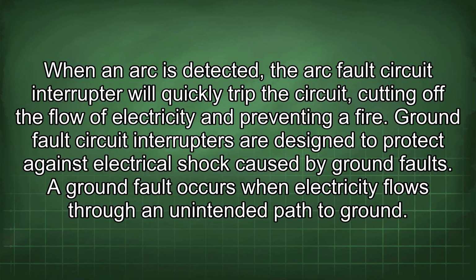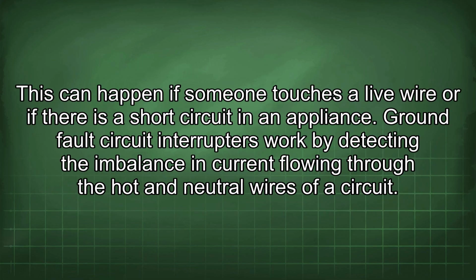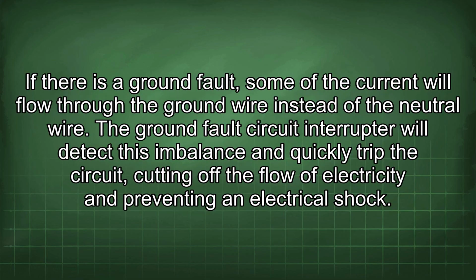Ground fault circuit interrupters are designed to protect against electrical shock caused by ground faults. A ground fault occurs when electricity flows through an unintended path to ground. This can happen if someone touches a live wire or if there is a short circuit in an appliance. Ground fault circuit interrupters work by detecting the imbalance in current flowing through the hot and neutral wires of a circuit. If there is a ground fault, some of the current will flow through the ground wire instead of the neutral wire. The ground fault circuit interrupter will detect this imbalance and quickly trip the circuit, cutting off the flow of electricity and preventing an electrical shock.